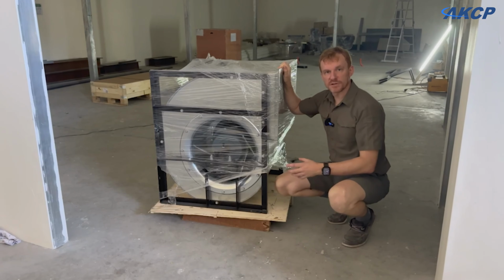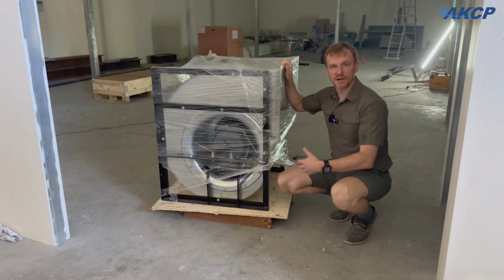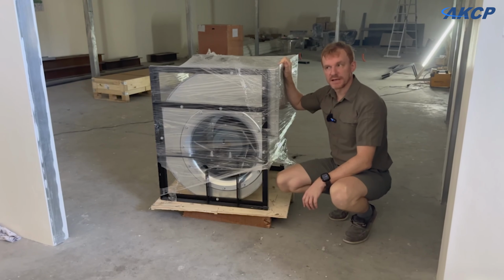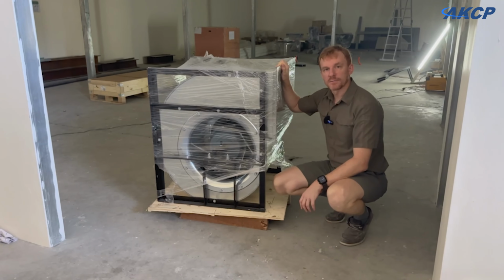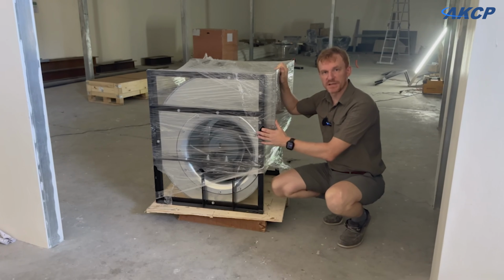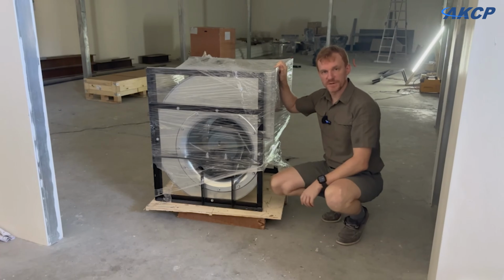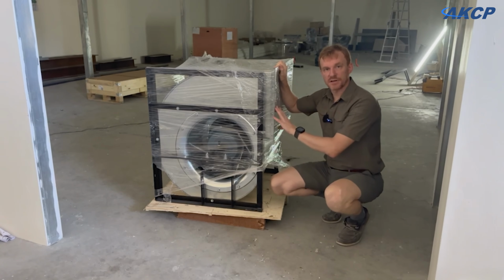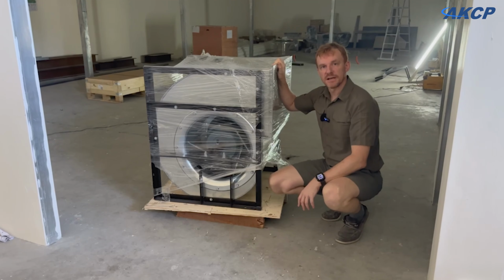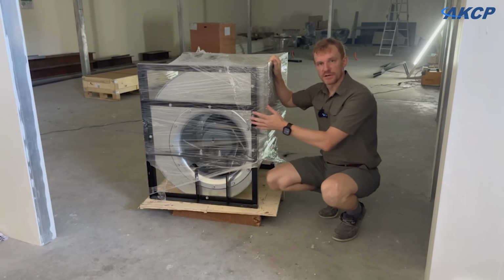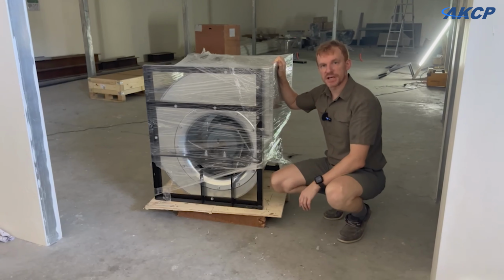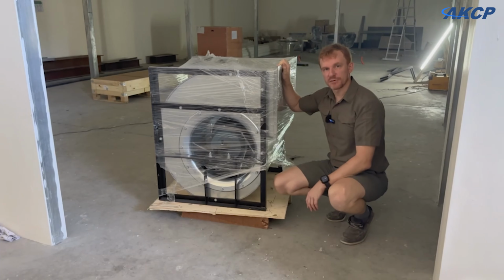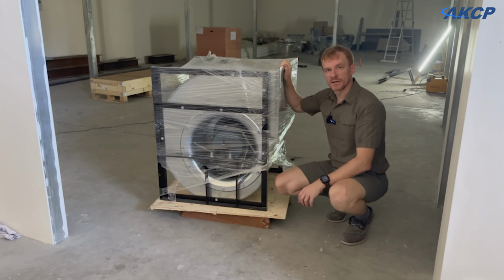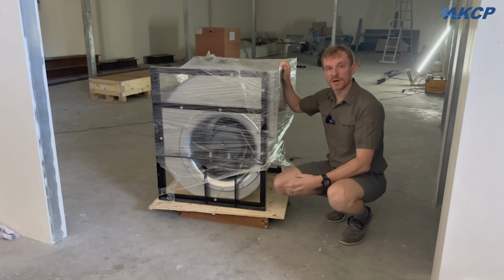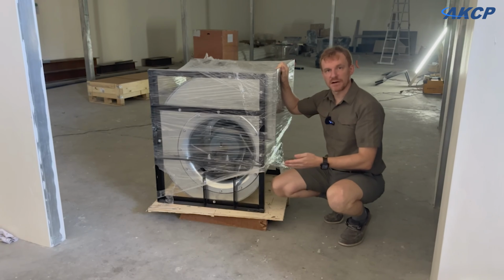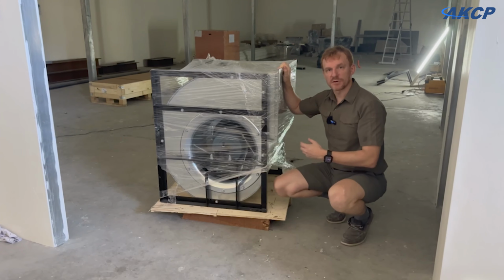As well as the data center, we also have an area in the facility for making presentations, an office area, and a monitoring room, which we also need to cool. We're going to use this centrifugal fan that's just been delivered to blow air into that part of the facility. Duct work will carry the cold air to the non-data center areas, cool those, and return warm air back to the fan, where there'll also be a heat exchanger cooling the air, connected up to our chilled water system. We'll be doing more videos in the coming weeks looking deeper into our cooling system and how we're making it more efficient.